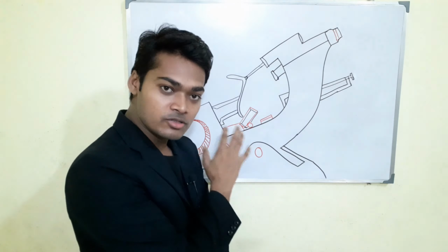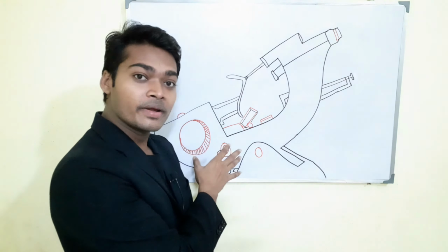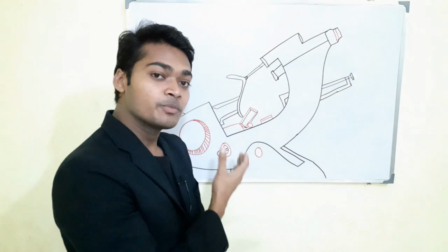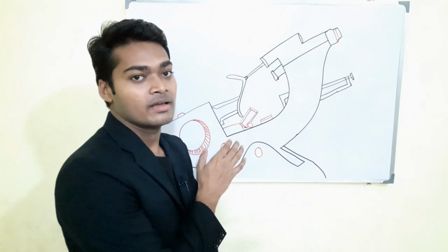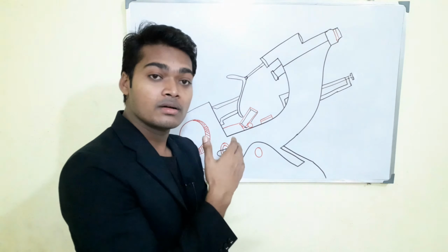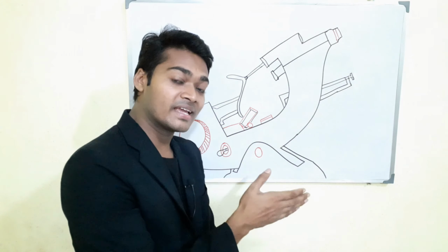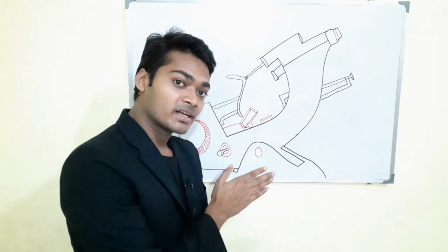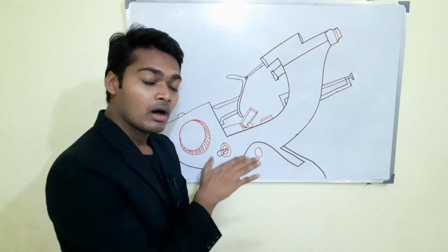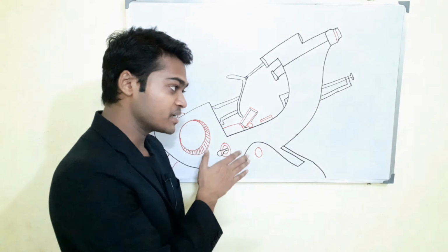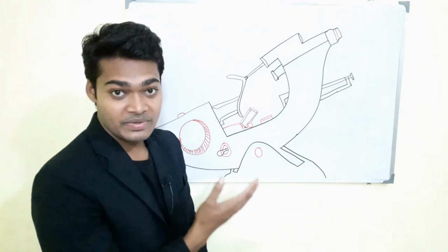The lensometer. This is also part of ophthalmic instruments, a very useful instrument to measure the present prescription that the patient wears, because according to the patient's complaint, sometimes it is very hard to distinguish whether the complaint is related to their spectacles or not. So find out the present value of the habitual spectacles the patient gives you: sphere, cylinder, axis, prism.